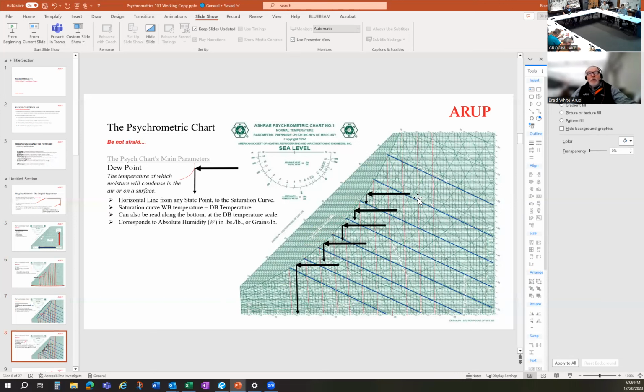So there's dew point. Any point on this chart, if I go straight to the left and I hit that saturation point, that will intersect with a dry bulb temperature, and that'll tell you at what temperature that will condense. So if you've got your proverbial glass of iced tea or beer, and you're outside on a hot summer day, and that beer is 42 degrees, you could say, well, I'm going to condense at a fairly cold temperature. Anything higher than your temperature, it will condense. You'll just get beads of moisture on your beer, and that's pretty much the end of it. But it just gives you an indication. That's useful for understanding how a cooling coil works. A cooling coil has to be at your dew point or below to remove any moisture.